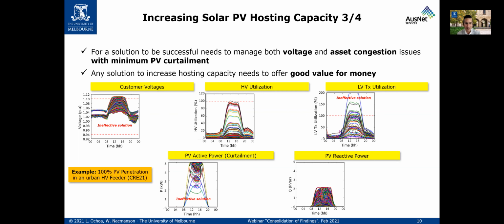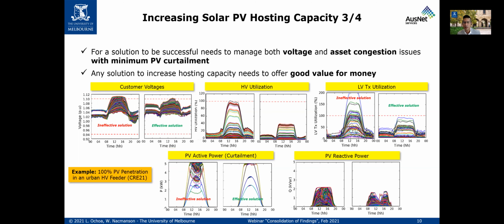I'm not going to tell you which solutions these are, but I'll present values to contrast an urban feeder at 100% penetration, where customer voltages are already beyond 1.1, and the distribution transformers at low voltage are already congested. The moment we apply another solution, all these metrics, all this performance, improve significantly from a technical perspective. From the customer's perspective—here you can see PV active power and curtailment—an ineffective solution will make most photovoltaic systems curtail, because voltages are too high, following, for instance, the PV inverter settings here in Victoria.